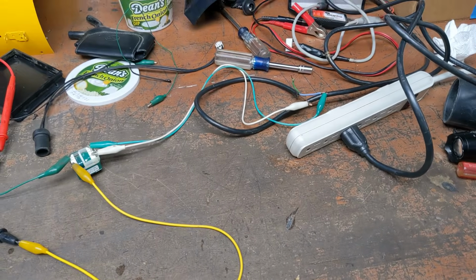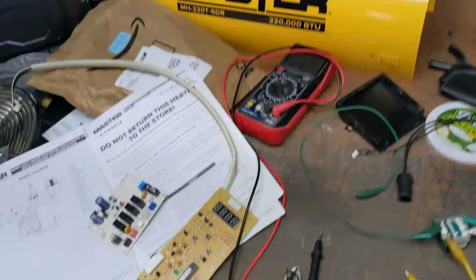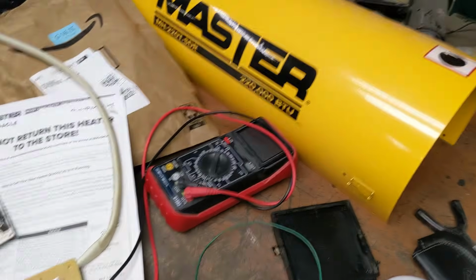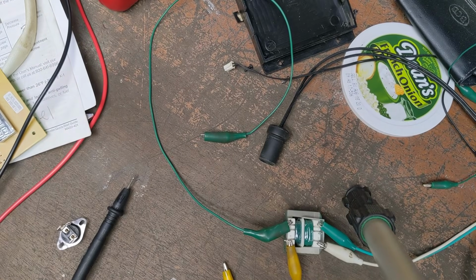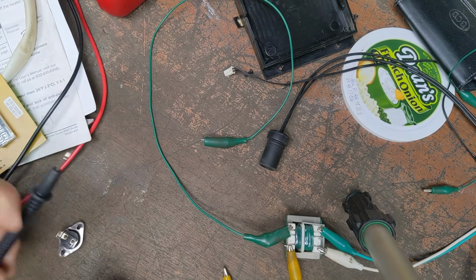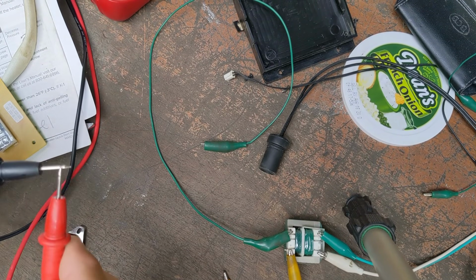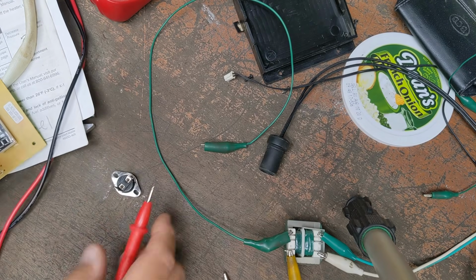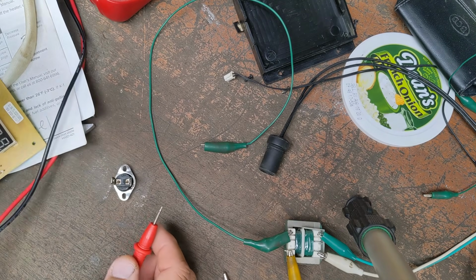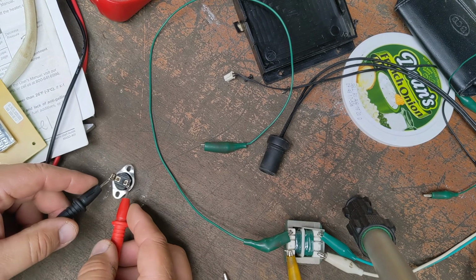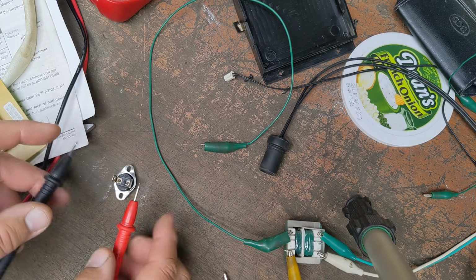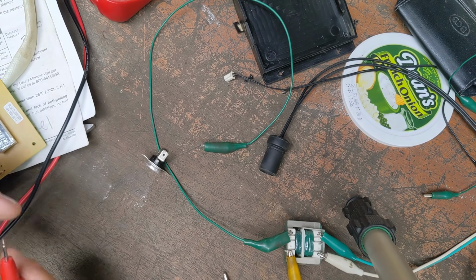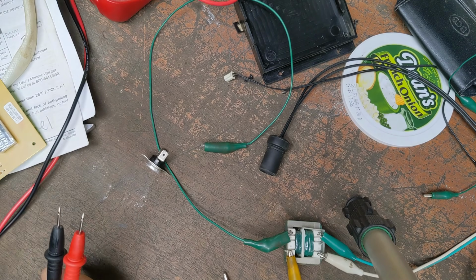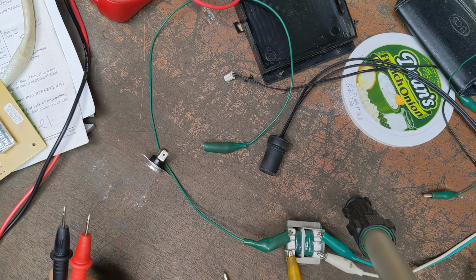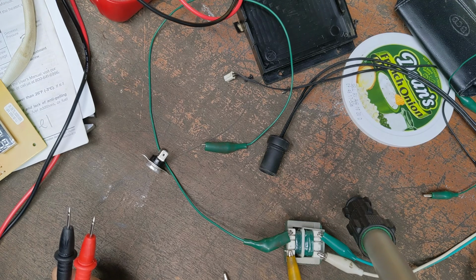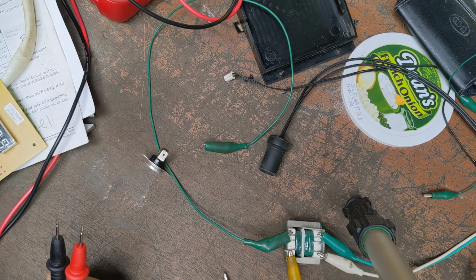All right, next step. Just to show you - this is just on continuity. There's the thermal probe I wanted to see. I didn't know if it's always open or always closed. So it's closed until and if it trips. The other one over there on the machine is the same way - normally closed, and if it gets too hot, it breaks the connection.